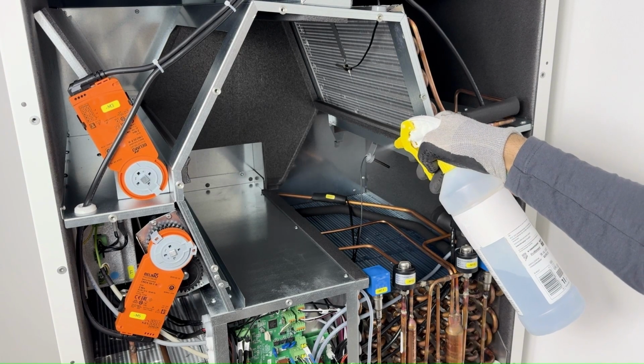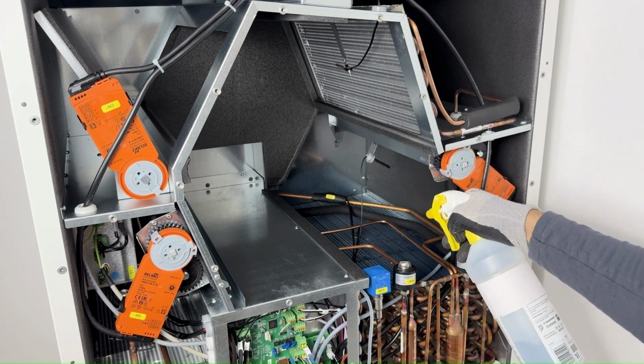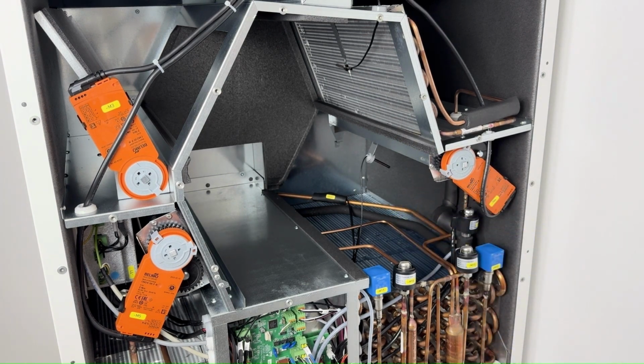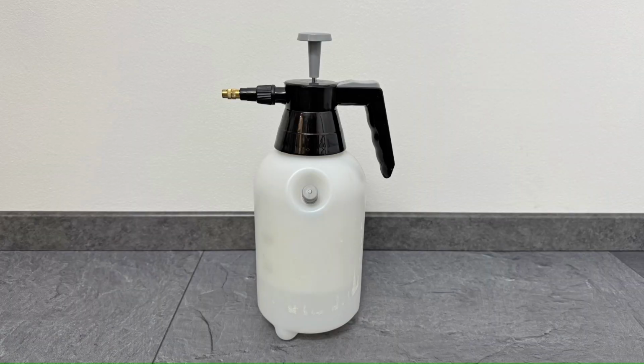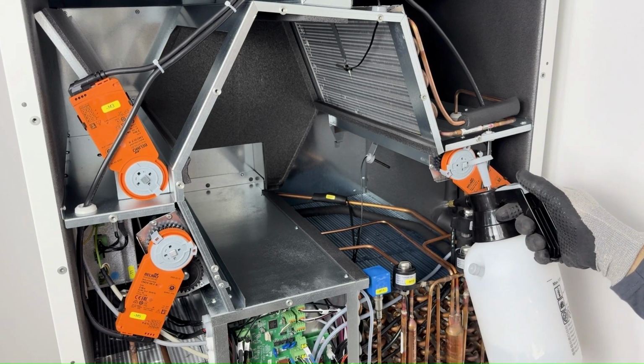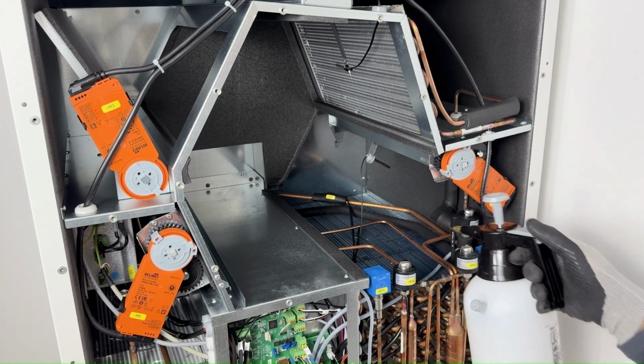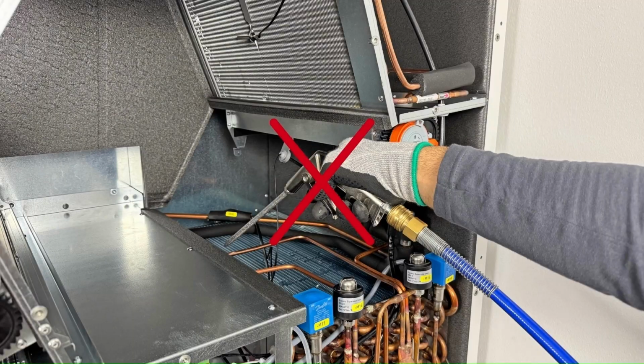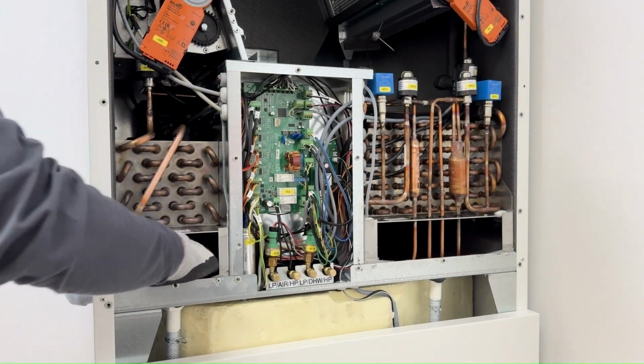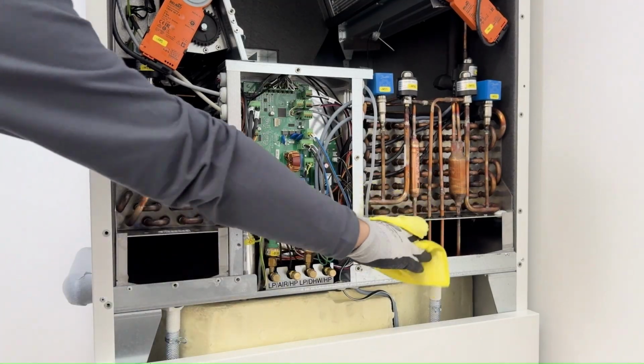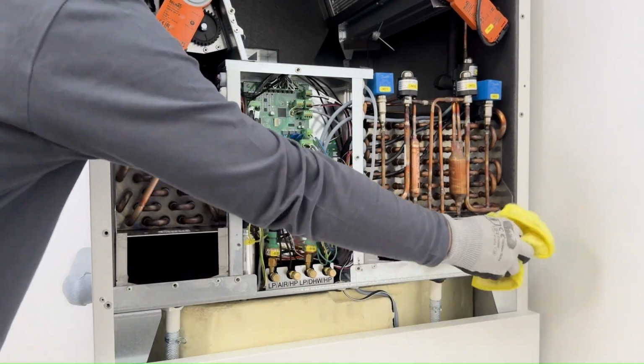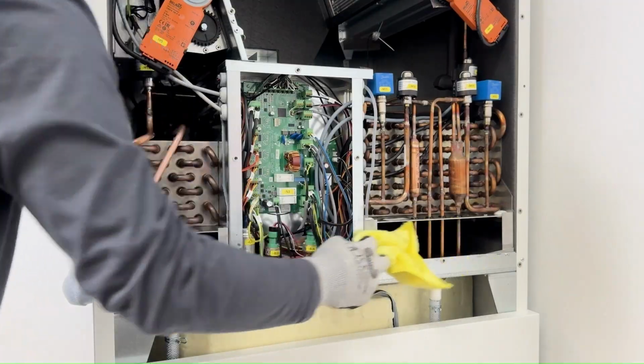Carefully spray the cleaning agent onto the surface of the heat exchanger and leave it to work for 2 to 3 minutes. Then take a spray bottle with lukewarm water and spray the heat exchanger until the cleaning agent and dirt have been completely removed. Avoid using hard brushes, compressed air, or high-pressure water so as not to damage the fins. Finally, clean the condensate trays for the supply air and exhaust air ducts by simply wiping them with a cloth. Please also pay attention to the fins of the heat exchanger.